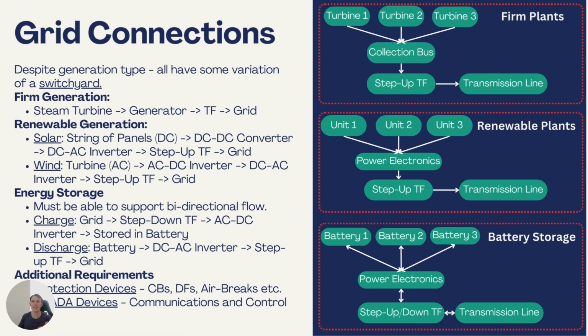To discharge, that DC power from the battery is put through a DC to AC inverter to put it into an AC system. This AC power is then stepped up using a step-up transformer to transmission level voltages, and then exported to the grid. So the discharge is essentially the same as renewable generation, but having that charge functionality is key. This charge-discharge functionality can be accomplished with the same infrastructure, but we've got to make sure the tap changer on the step-up/down transformer has enough range to manipulate the windings on the high side and low side to ensure the voltages can be stepped down correctly.